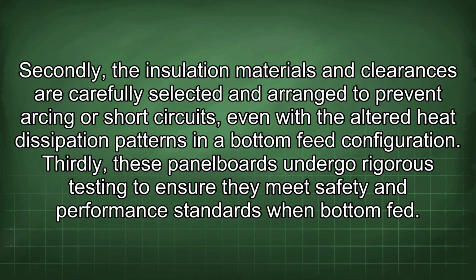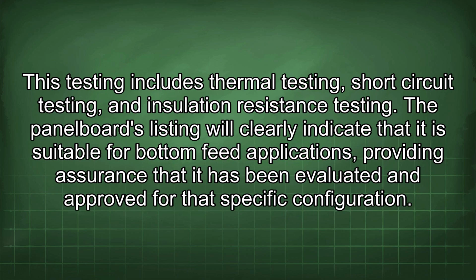Secondly, the insulation materials and clearances are carefully selected and arranged to prevent arcing or short circuits, even with the altered heat dissipation patterns in a bottom feed configuration. Thirdly, these panel boards undergo rigorous testing to ensure they meet safety and performance standards when bottom fed. This testing includes thermal testing, short circuit testing, and insulation resistance testing.